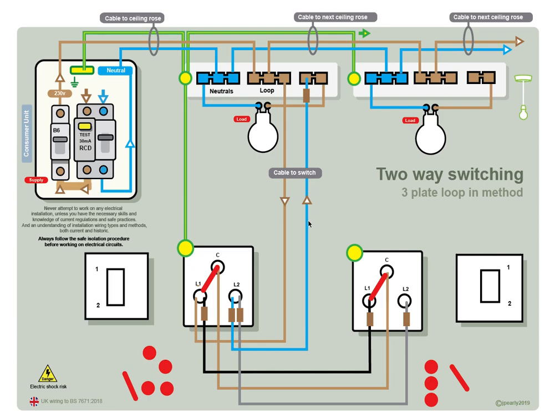And let's follow the flow and see if it gets to the actual light. So we're leaving the power, comes in, goes via a protective device. In this case it's a 6 amp MCB. It's 230 volts, so it's mains voltage, so good care is needed to be taken. Power leaves the consumer unit, comes into the ceiling rose where there's three connections: one connection for the power in from the consumer unit, one connection for the loop into the next ceiling rose, one connection for a permanent live down to the light switch.